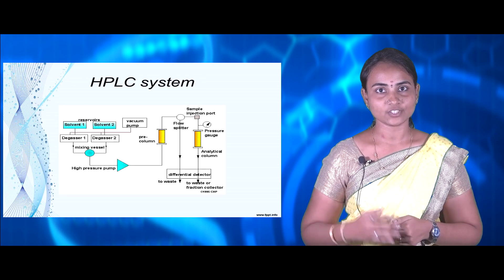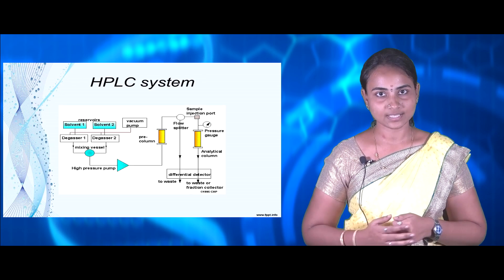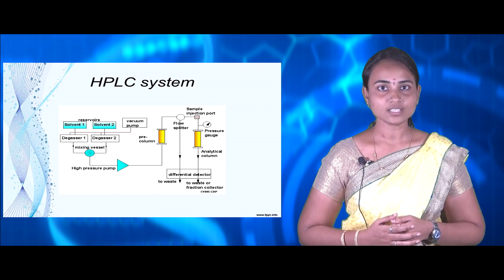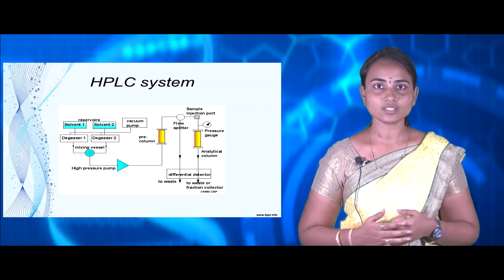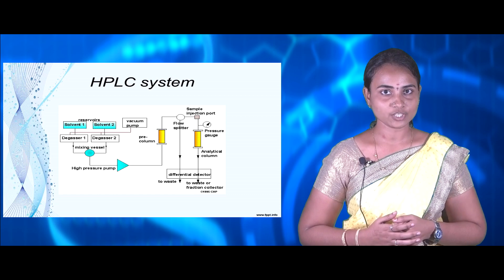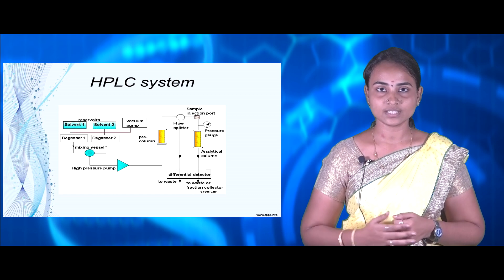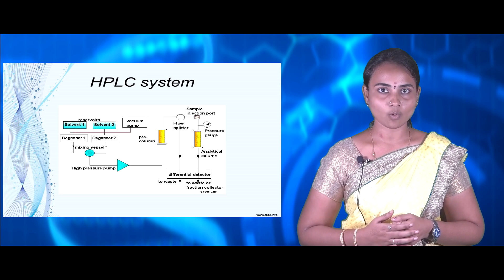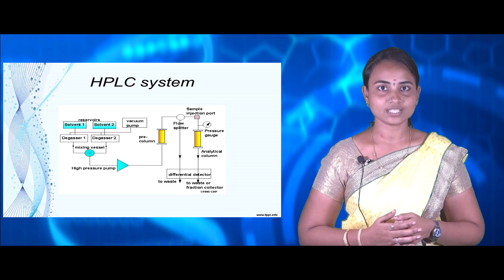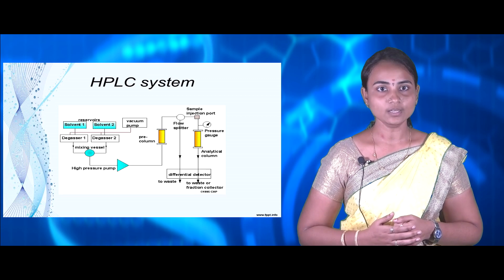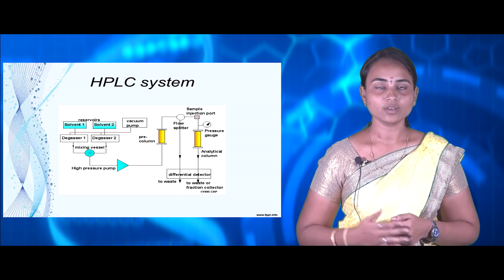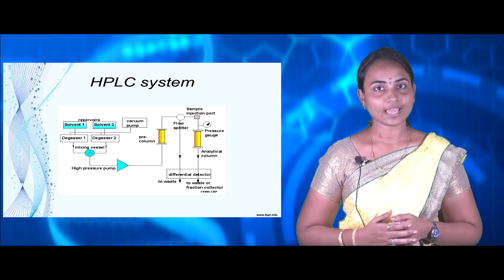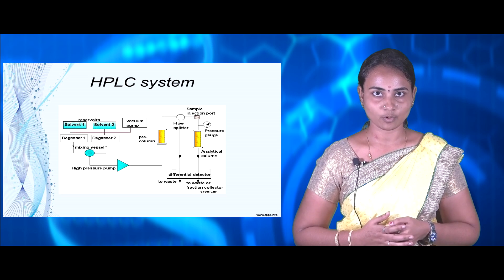This diagrammatic representation shows the HPLC system, which has two different reservoirs for solvent, allowing combinations of different solvents to be used. After the reservoirs, the flow is connected to a degasser to avoid air bubbles, then to a mixing vessel, and then to a high pressure pump to push solvents into the pre-column, which is connected to the sample injection port.